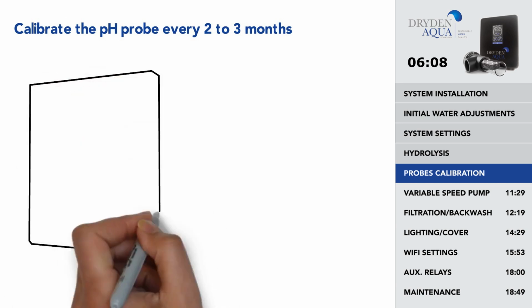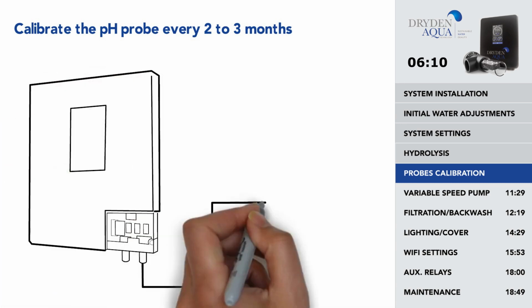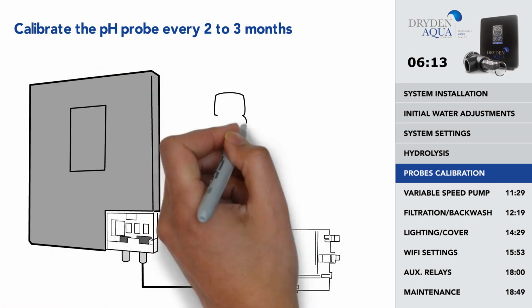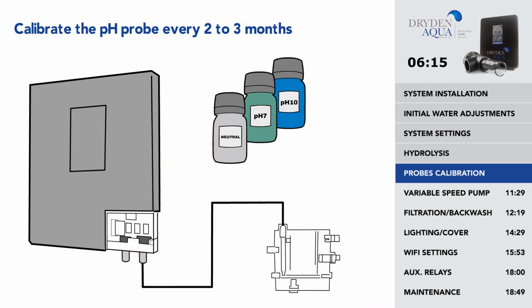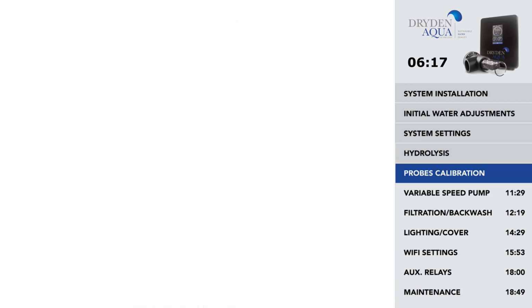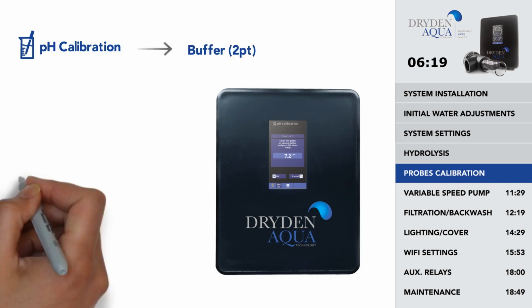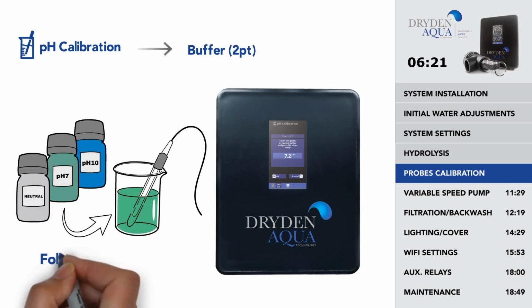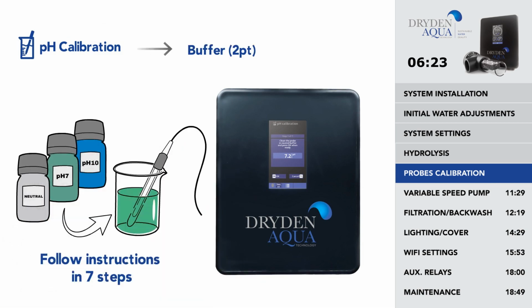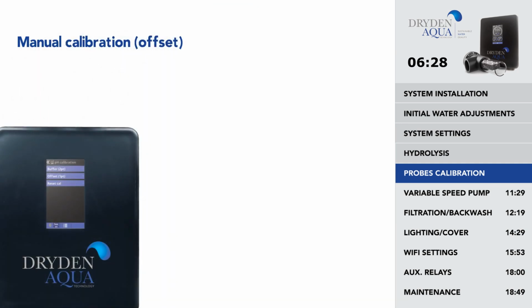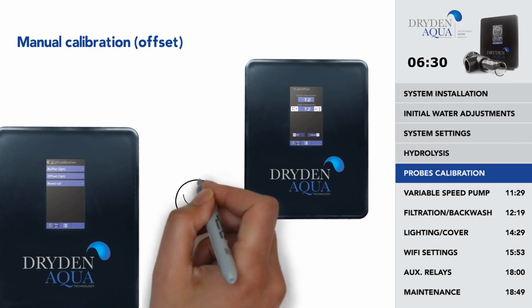It is recommended to calibrate the pH probe every 2 to 3 months during the usage season, and to always do the first calibration with the buffer using the provided buffer solutions. To do that, press on Buffer on the screen and follow the instructions that appear on the display. Manual calibration of the pH probe is also possible, but only recommended to correct small deviations in the readings.